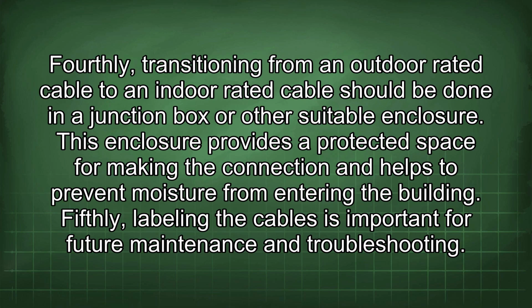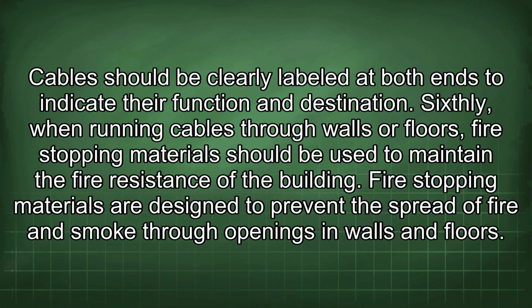the building. Fifthly, labeling the cables is important for future maintenance and troubleshooting. Cables should be clearly labeled at both ends to indicate their function and destination. Sixthly, when running cables through walls or floors, fire-stopping material should be used to maintain the fire resistance of the building. Fire-stopping materials are designed to prevent the spread of fire and smoke through openings in walls and floors.